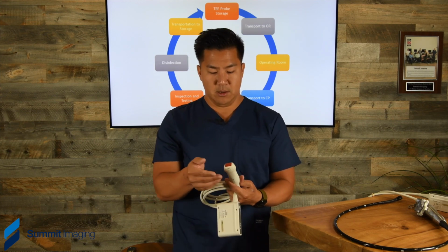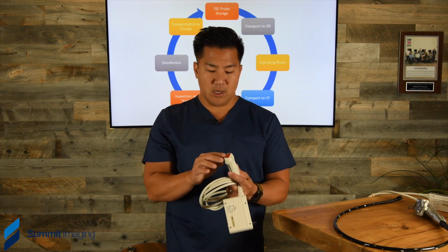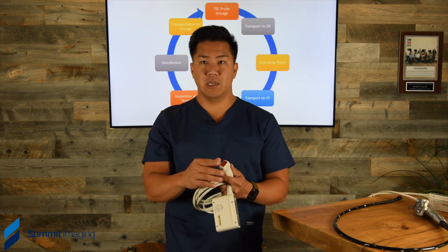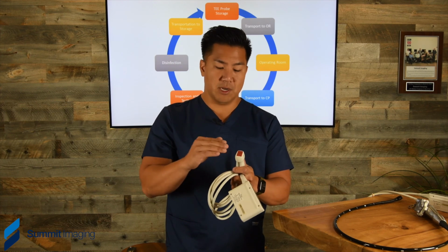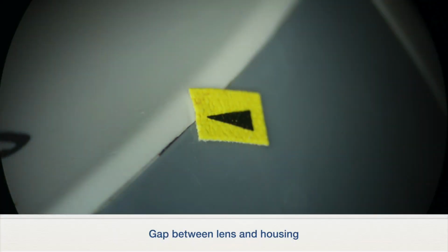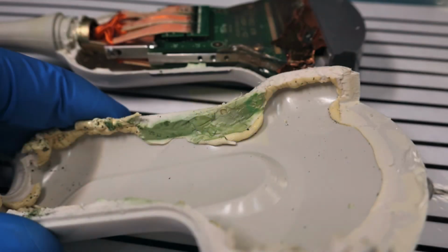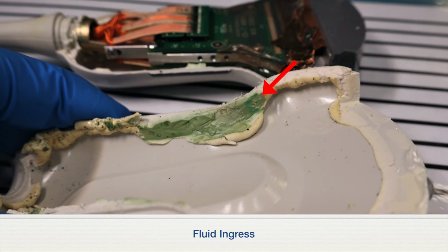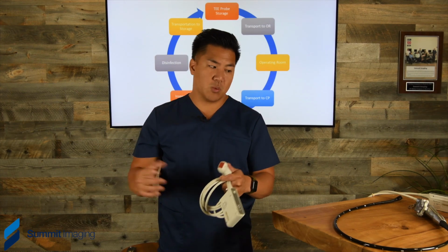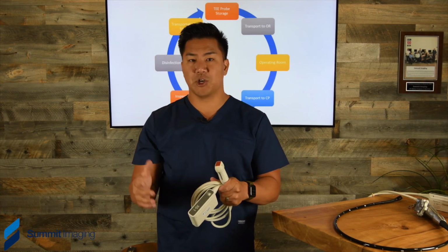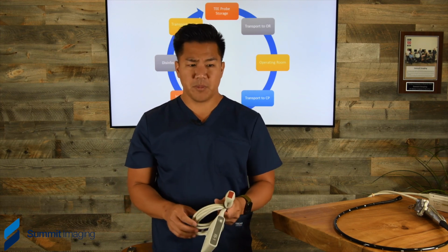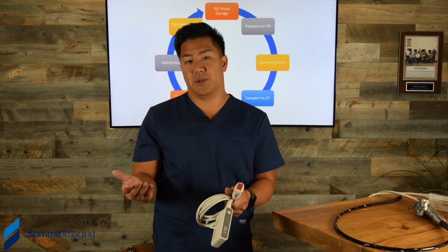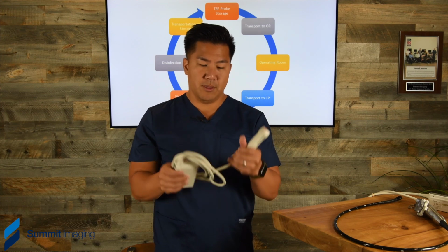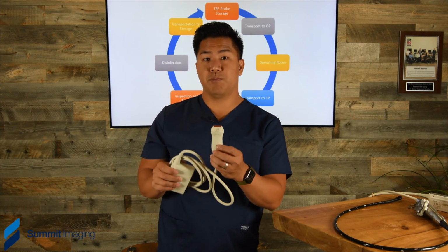Another one is as you're wiping these probes down, be gentle as you're wiping it. We've seen some technicians wiping it so hard that it starts pushing the lens away from the edge, and now you've got a gap. And then once that gap is there, you throw on some ultrasound gel, and that fluid then penetrates into there, corrosion begins, and that's when the failures really start to occur. And then the electrical properties of the probes are now vulnerable to the patient. And so that's something to look for on these probes as well.